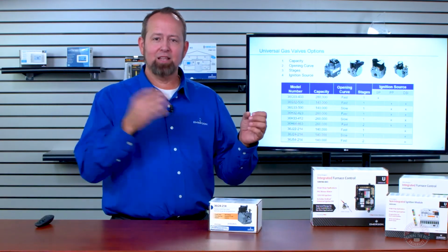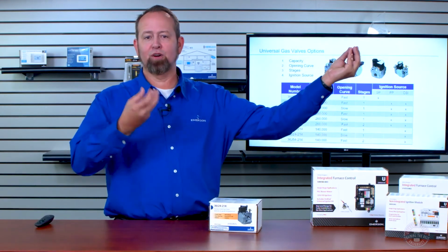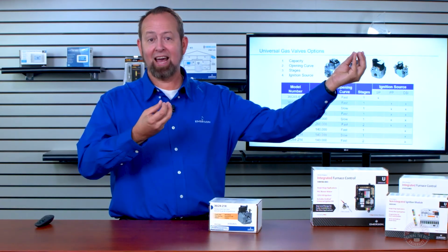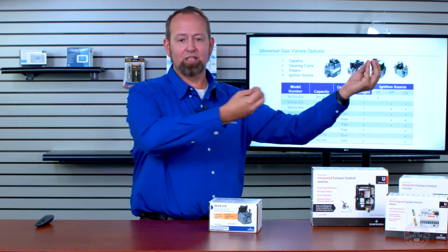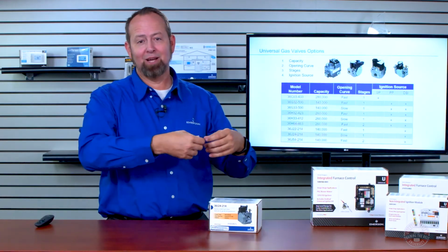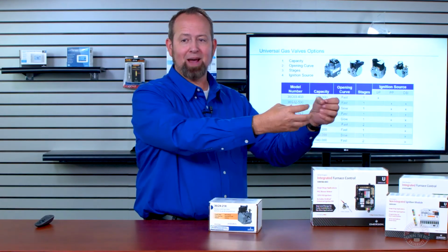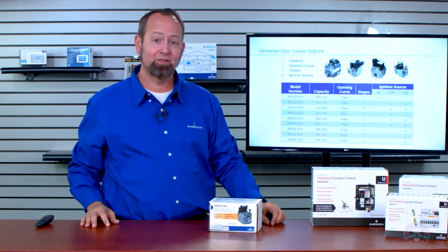If gas came in those too fast, gas could be coming up the back before the front actually had ignited, and by the time the ignition traveled to the back, you had an explosion, and sometimes it used enough oxygen at the back that it'd blow the whole thing out, sometimes even the pilot.